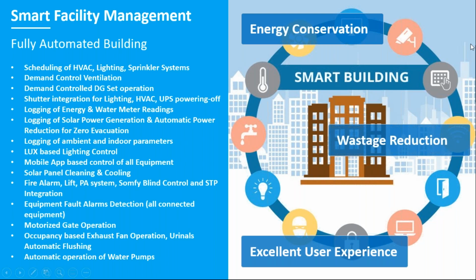Something specific worth mentioning: we do solar panel cleaning and cooling using the building automation system. We have a sensor on the solar panels that reports their temperature, because once they reach a certain temperature, they start losing efficiency for every degree of rise. So if these panels are cooled periodically, the efficiency improves automatically.